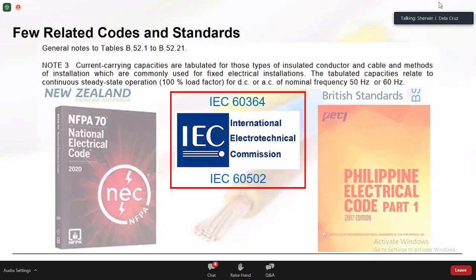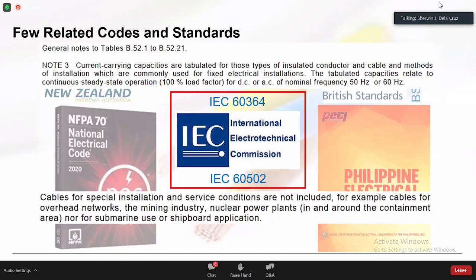Another disclaimer: cable sizing based on IEC 60364 is applicable only to fixed electrical installations. Cables for overhead lines, mining, nuclear power plants, submarine, and shipboard are not applicable. Fixed installations include power plants, oil refineries within process areas, substations, and buildings.